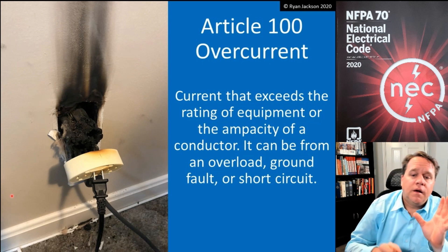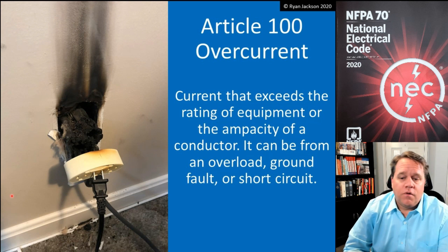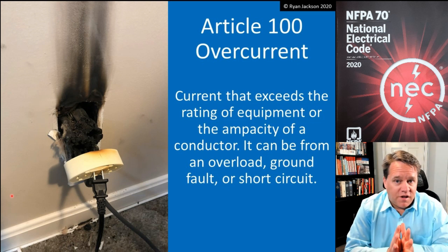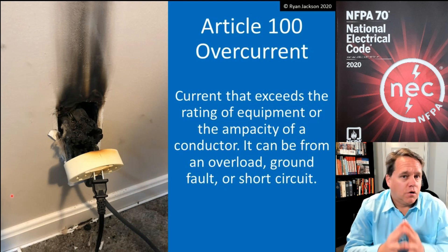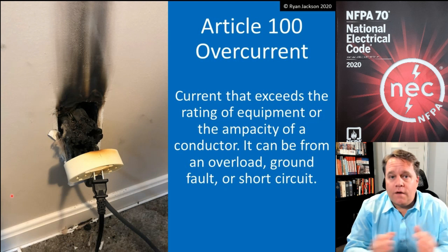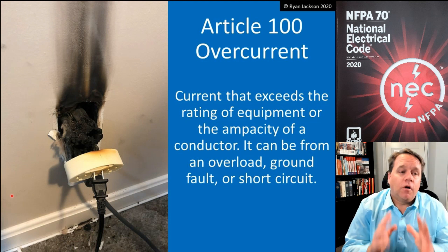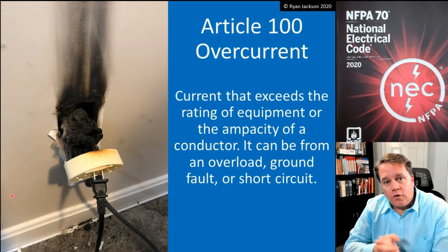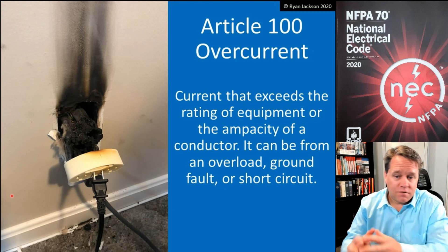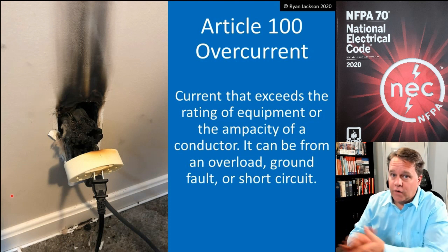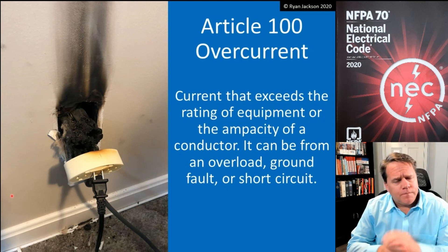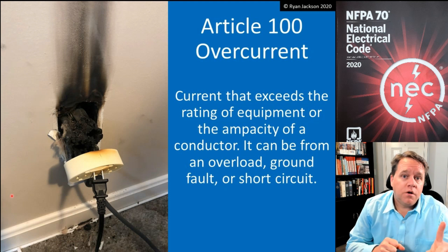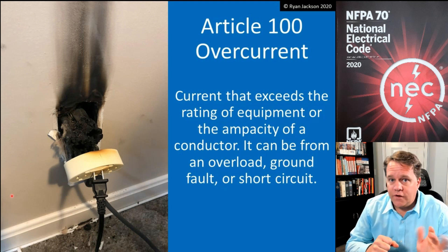Overcurrent can result from an overload, a ground fault, or a short circuit. It's really important to understand that you have to protect against all three — otherwise you don't have overcurrent protection. If all you have is overload protection, that's not overcurrent protection; it's overload protection. If all you have is ground fault and short circuit protection, that's ground fault and short circuit protection. Usually we protect against all three with one device, called a branch circuit overcurrent device.